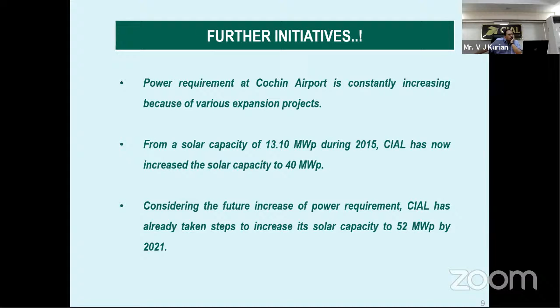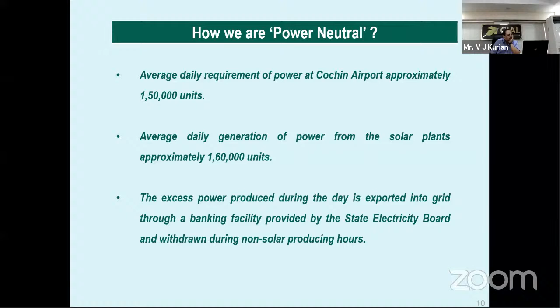Our average daily requirement of power at Cochin Airport is around 150,000 units, and our average daily generation is approximately 160,000 units, giving a surplus of around 10,000 on average every day. So we produce our entire 24-hour requirement during the solar power producing period, that is daytime, and whatever is excess is exported into the grid through net metering and banking facility provided by the Kerala State Electricity Board. We are allowed to withdraw the excess power at night when solar power is not available. We don't have any storage battery; we store our excess power in the grid.